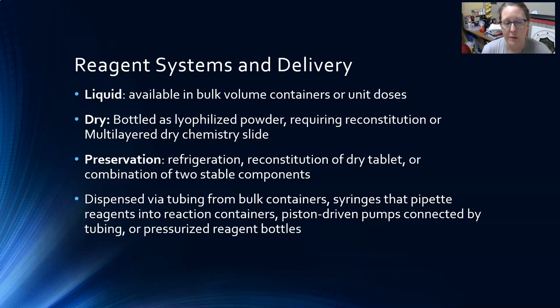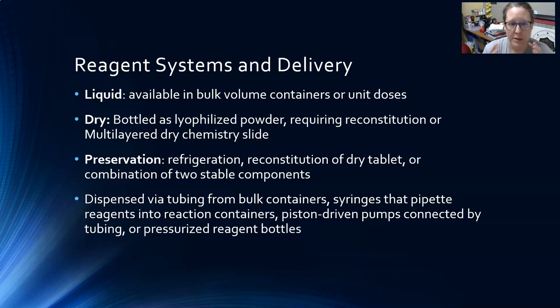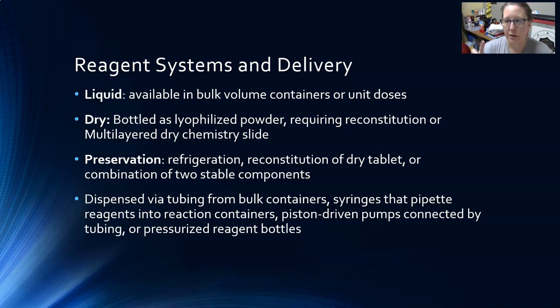The most common dry format now would be the multi-layer dry chemistry slide, using the Vitros line of analyzers. These are square dry slides loaded onto analyzers in stacks for each type of test. Once reagents are loaded onto the analyzer, they need to be preserved, often by refrigeration modules. A dry tablet or lyophilized powder may need to be reconstituted — good for a set amount of time after reconstitution, done by the analyzer by adding water or a reagent contained in a vial that is part of the reagent packet.